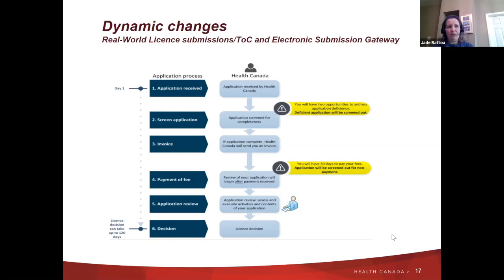We also have timelines for processing license applications. For example, we have 15 calendar days to process a class two license application, 65 days for class three, and 75 days for class four. But sometimes, because we give manufacturers the right to be heard, we go back to them to supply missing information through additional information requests or regulatory deficiency emails. That's how it works.